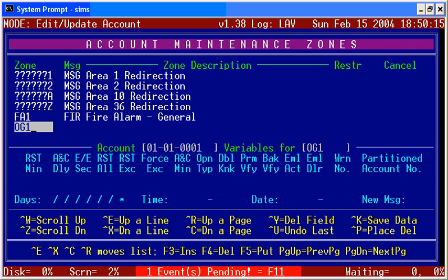and redirect them together. If you're using the SureGuard DVAC, note that just by definition of the way some of the direct wire or the multiplexing type signal systems work, they may go out and interrogate a panel, get one signal in, which might be an opening. They will then continue around through the loop of all other panels and then come around and ask for the second part of the information, which might be the group identifier.